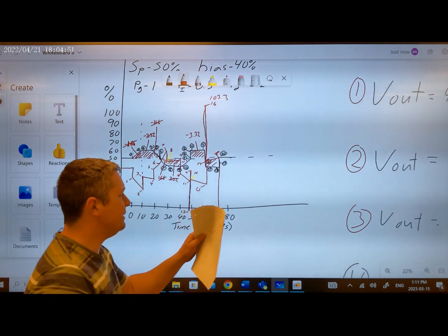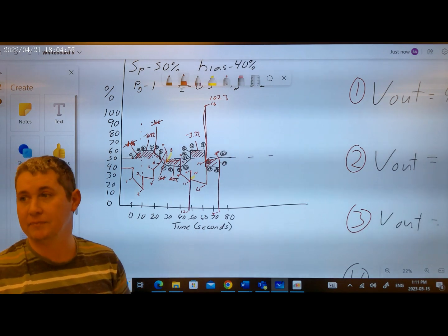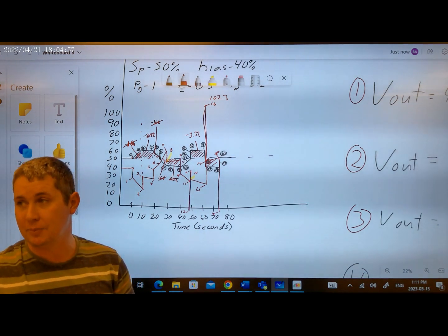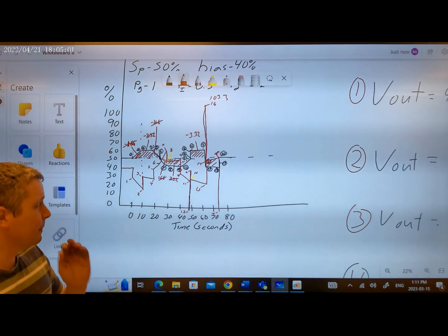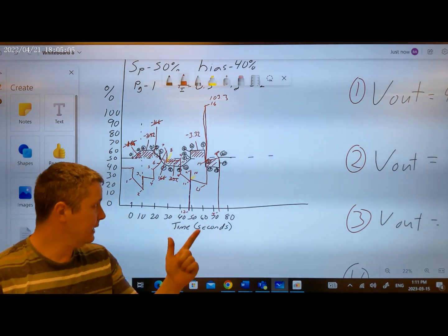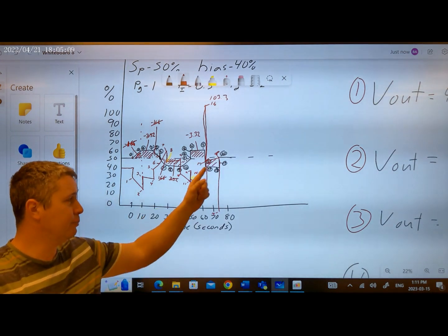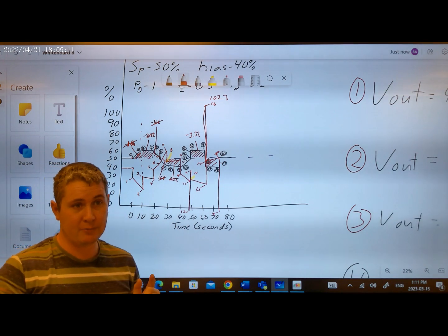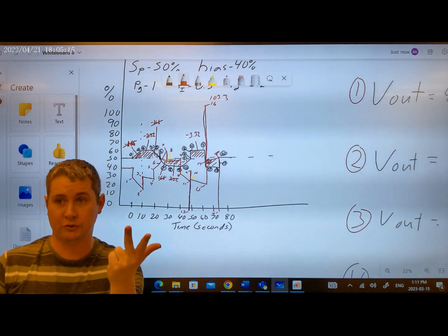And now 20 is back up to its set point. Now without calculating it, just thinking about it, we have no old integral, we have no new integral. It's an instantaneous spot right here, but we have plateaued, so the ramp rate is 0, so we have no derivative. No old integral, no new integral, no derivative.